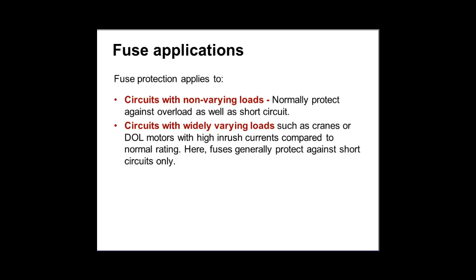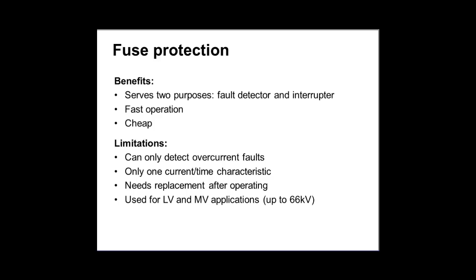You must be very careful about what would happen if you lose that feeder. You are going to save a lot of money by replacing the relay with a fuse, so you have to be very, very careful. Benefits: cheap, fast operation, serves two purposes, fault detector and interrupter. However, limitations: can only detect overcurrent faults, only one current-time characteristic, and needs replacement after operating. Used for LV and MV applications, max up to 66 kV, and again, not for main feeders. I can add to the limitations, as we discussed, that fuses are affected by aging, dust, corrosion, and humidity.